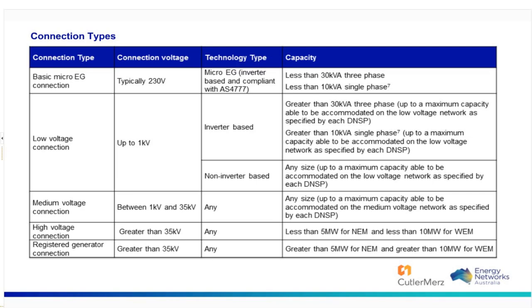And then the high voltage is obviously at greater than 35 kV, which departs somewhat from the Australian standard requirement, because the Australian standard defines HV as greater than 1 kV, but because we've created this new medium voltage definition, it means the high voltage then gets pushed to 35. And then the capacity of those connections will be anything up to 5 megawatts on the east coast or 10 megawatts on the west coast.